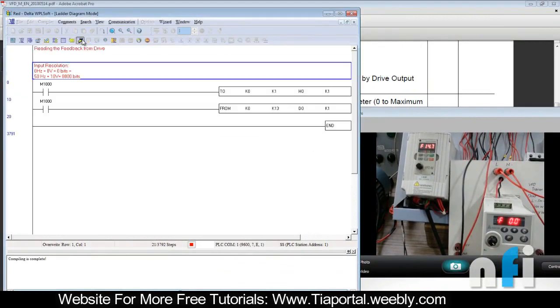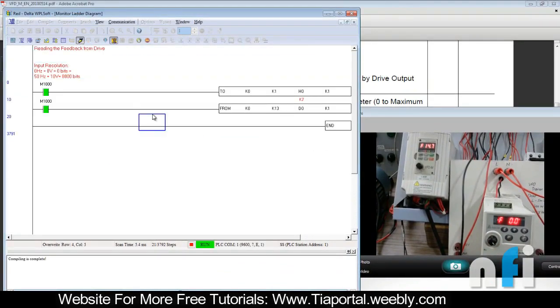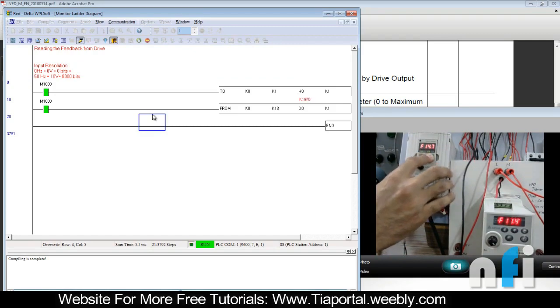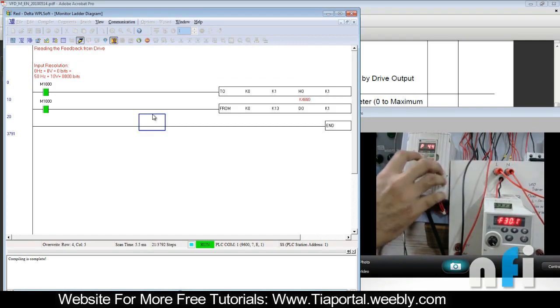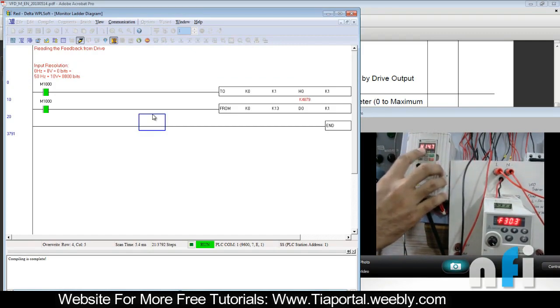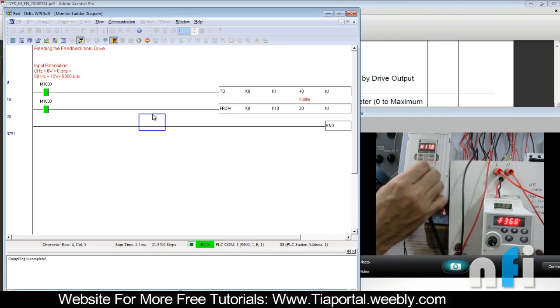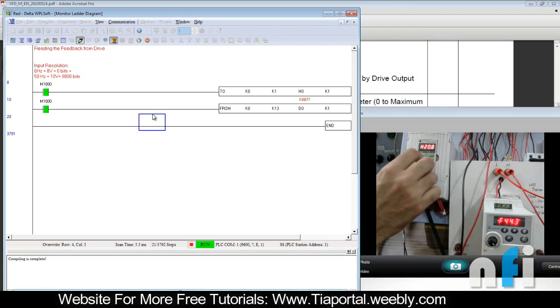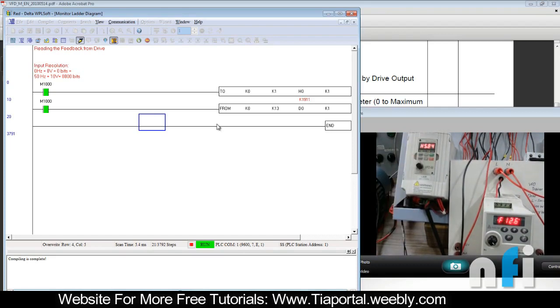This card has 14-bit resolution. When the drive is off there is no feedback — just a noise signal of 6 to 7 bits. When the drive is on you receive the feedback, which is the output frequency. Because the gain was set to twice (200%), at 25 Hz you get 8000 bits, showing the effect of the gain setting.